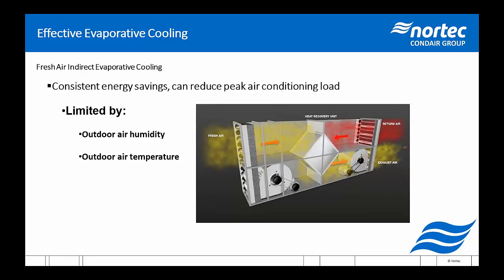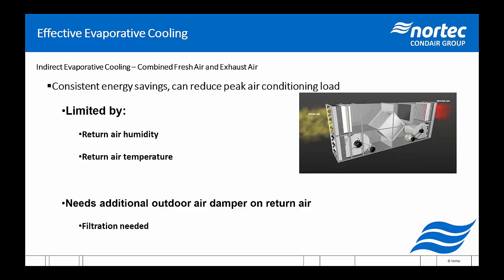We can actually combine those two technologies, where this is the exact same diagram as before, but we could put in a damper just before the humidifier after the return air to pull in outdoor air when it's more appropriate to use the outdoor air for cooling. That's not something we've seen applied very much yet. There is a filtration need, obviously, for that. There would be an additional pressure drop to discuss, but it is a method that could allow for a few extra kilowatt hours savings per year.